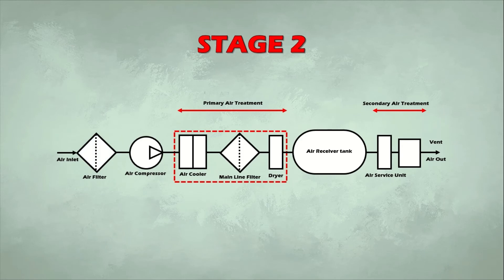The air from the compressor is treated in the second stage. The temperature is lowered using a cooler, and the air is dried using a dryer. An inline filter removes contaminant particles. This treatment is called primary air treatment.